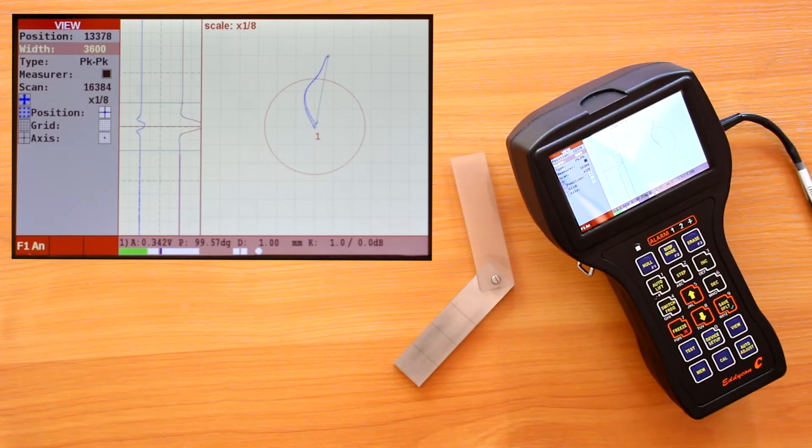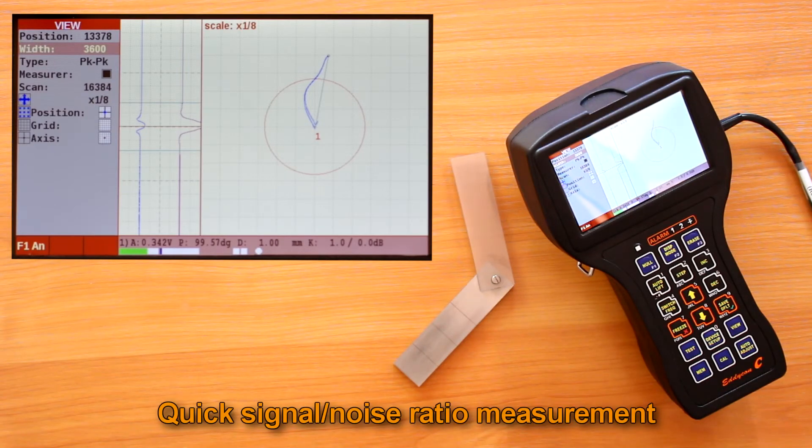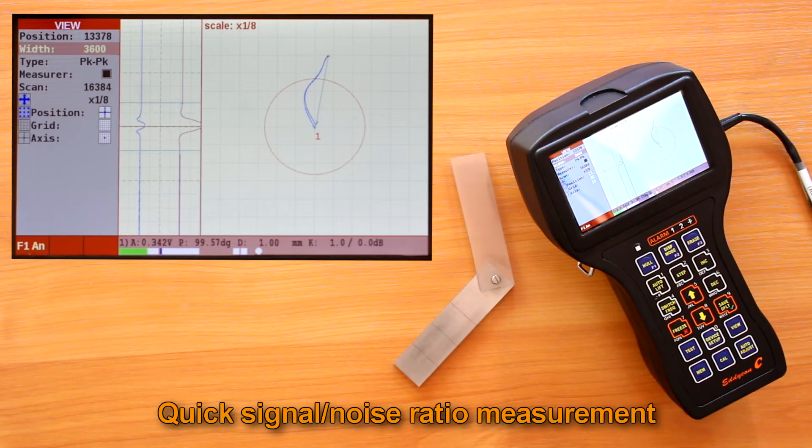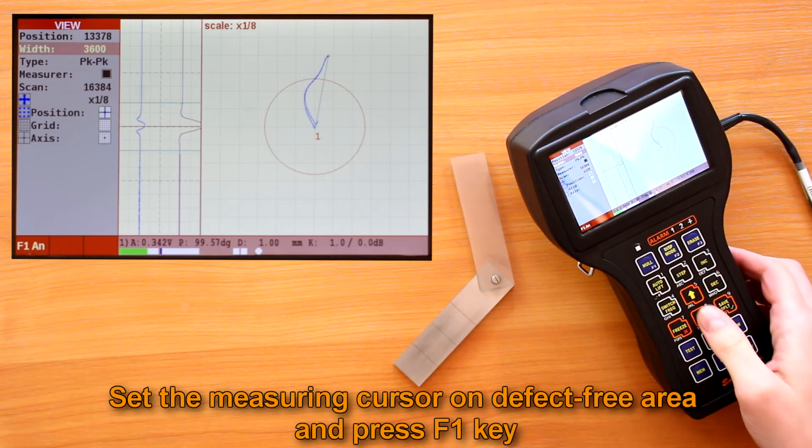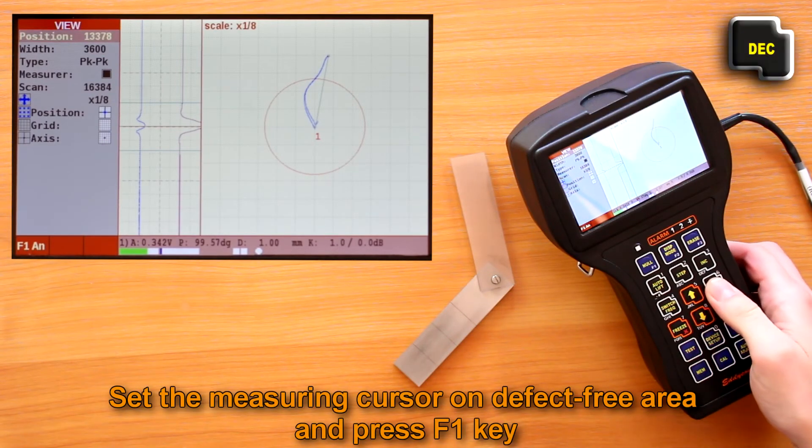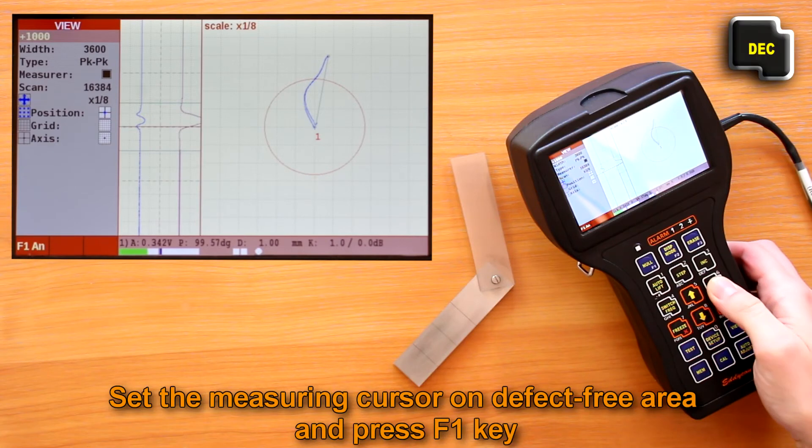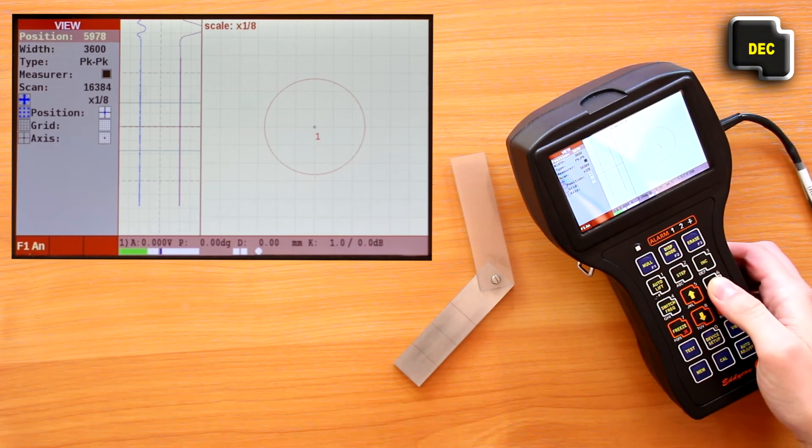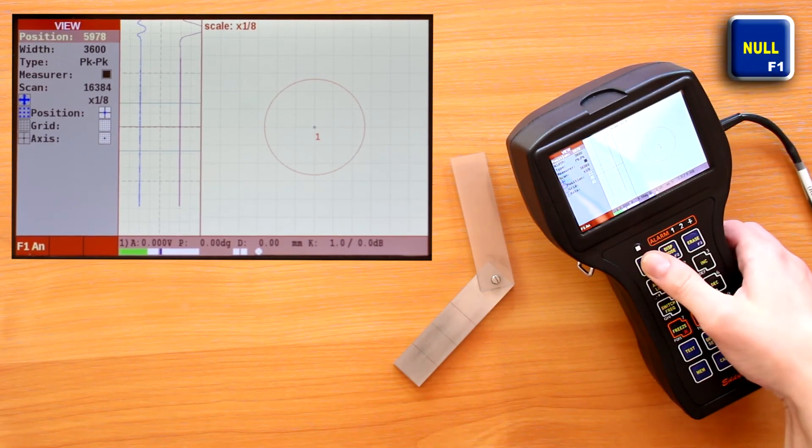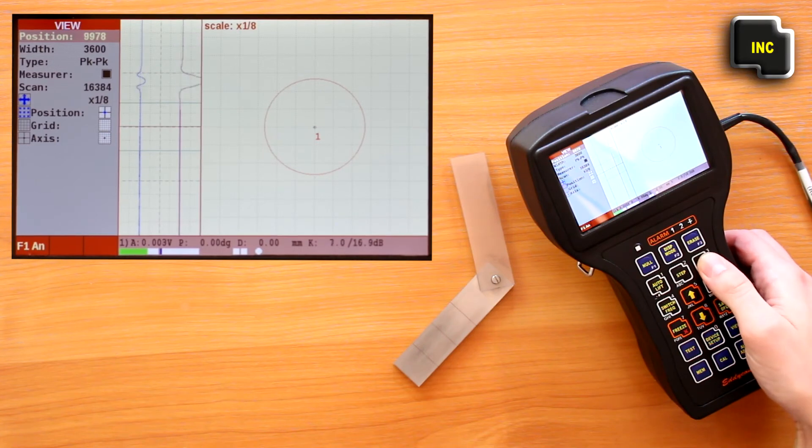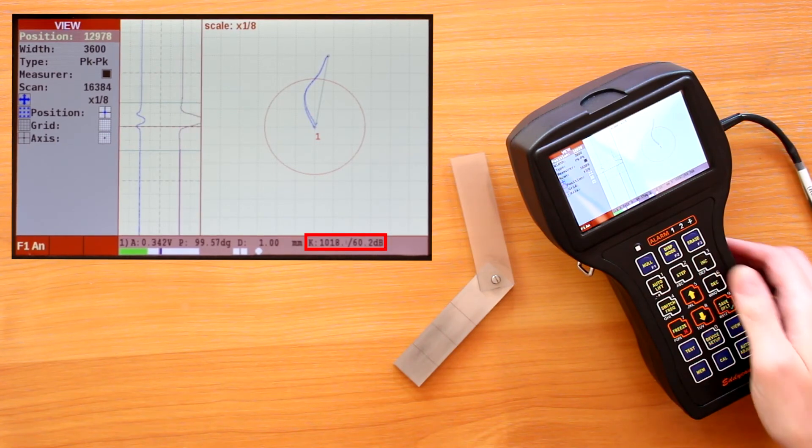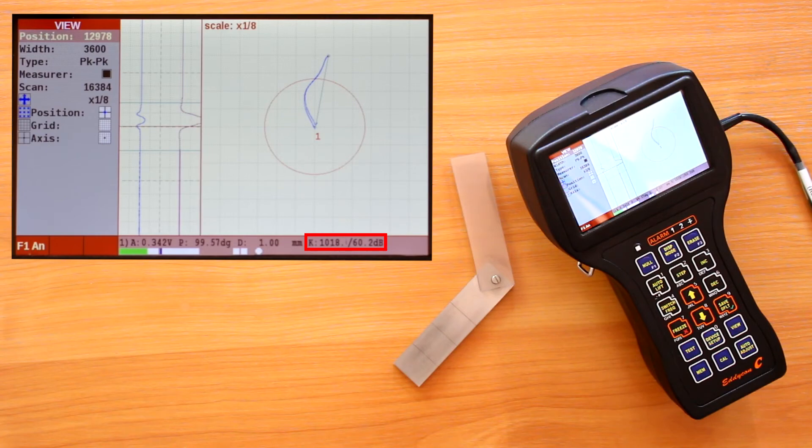The flaw detector has a feature that allows you to quickly measure the signal-to-noise ratio. First, set the measuring cursor on a defect-free area in the strip charts and press F1 key. Then move the center of the measuring cursor to the signal peak from a defect. The result appears in the right bottom corner as the measured signal-to-noise ratio.